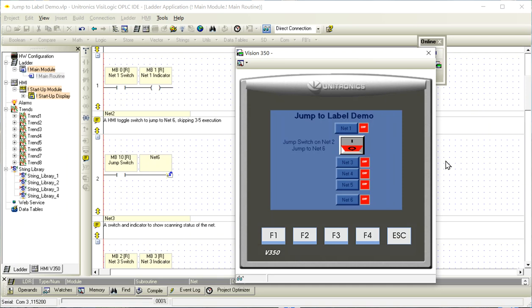Different PLCs implement this in different ways. Some go a little bit further along, and they'll call it a master control reset, and they set up a whole zone where none of the outputs could turn on at all. That's sort of like the relay logic world putting a master control relay into the actual ladder portion of the code, to cut off outputs for safety reasons or whatever, so none of those outputs would go on.